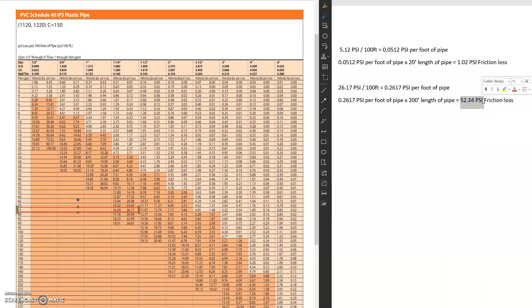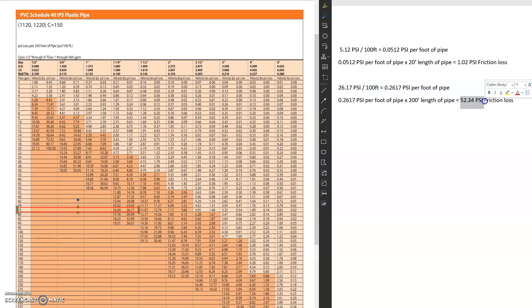So that's quite a bit of friction loss that we have through a system. Most residentials, you would lose almost your entire pressure at the house. And you'd have little to no pressure at the end of your system if you lost that much. Most homes, it's somewhere between 40 and 60 PSI is available. So when we're then losing 52, you have a substantial loss of your system.